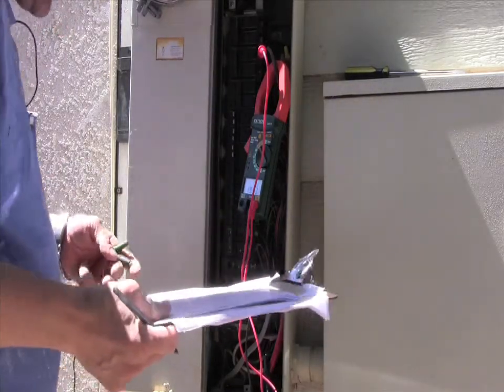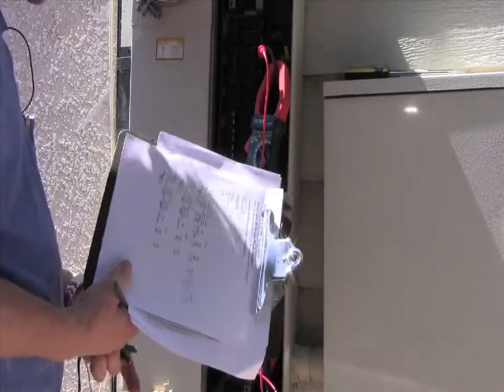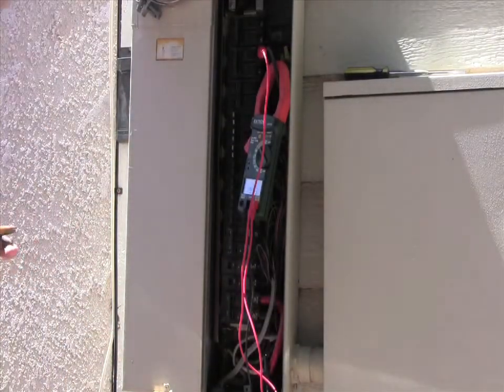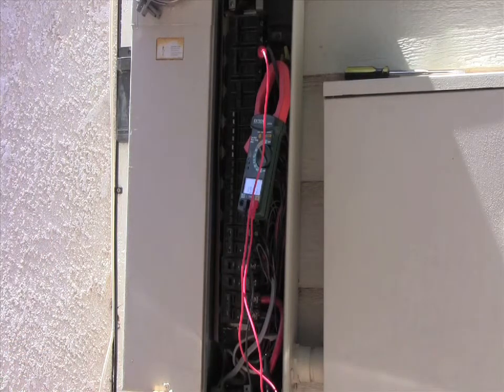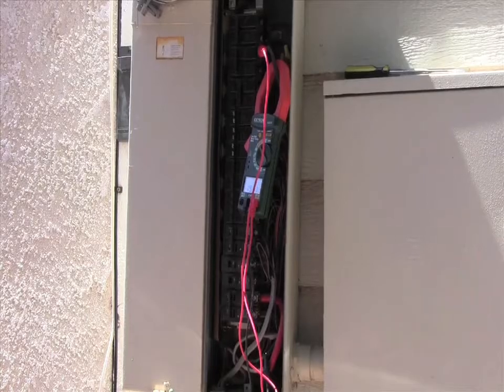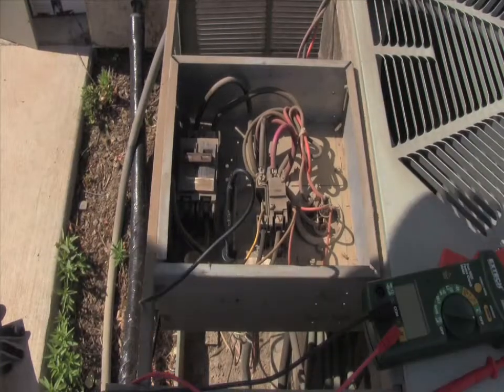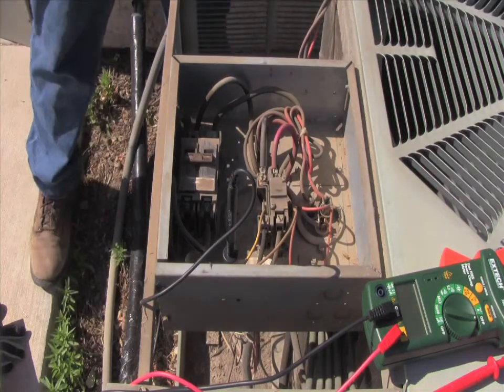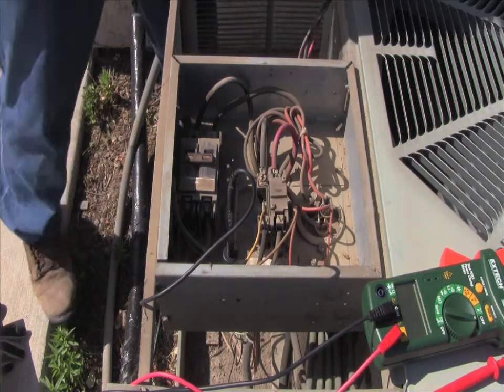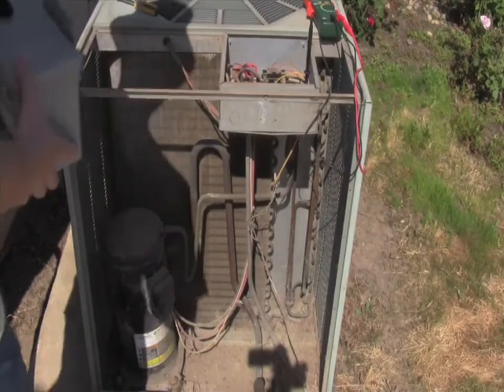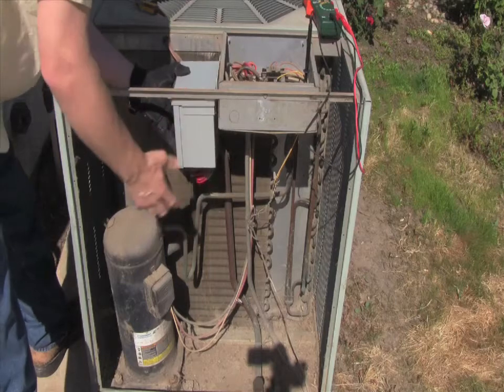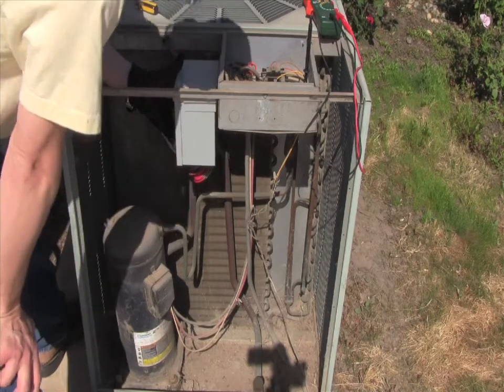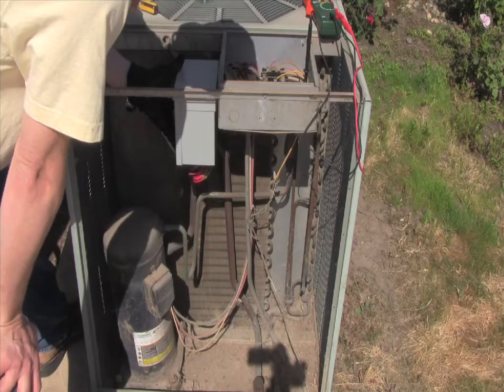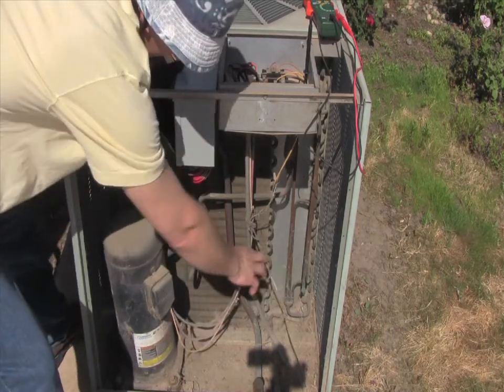Alright, so I'm going to go over and install the power cube, and we will come back and check the readings on installation. We need to find a suitable mounting location. Now this is going to be inside the unit, like so. And let me pull this over here so you can see what I'm talking about. So I can mount it right here on the side of the box, inside, and because it's inside the unit, it doesn't need any conduit, because as you notice, all these wires are loose. Everything in here is loose.